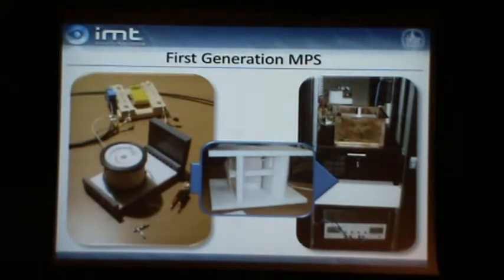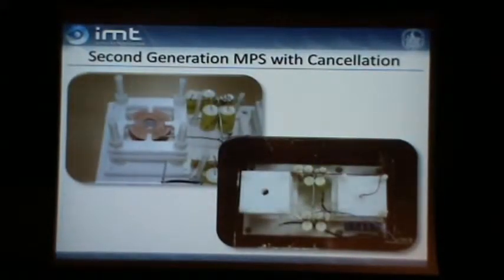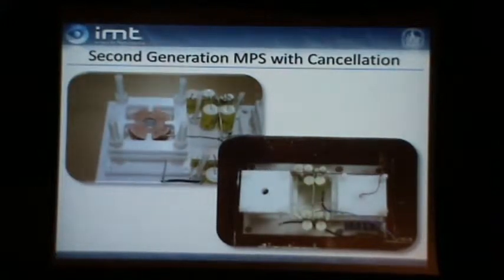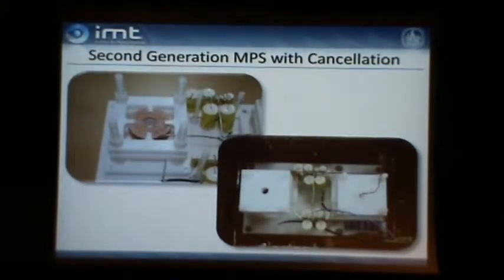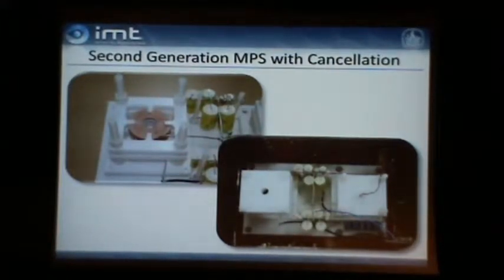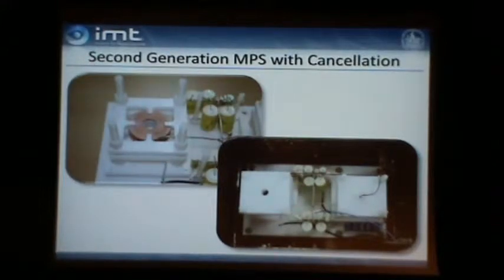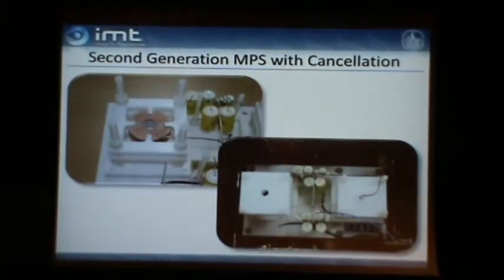The bandwidth is okay, but a cancellation technique is needed, and so the second generation MPS already has cancellation. You see we have some advances in producing coils, which look much more sophisticated, together with a capacitor bank here. And when you look in the shielding box, we have two mirror devices, which produce the same transmit signal.